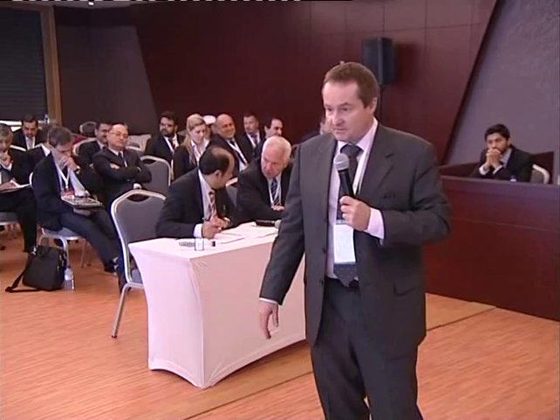Okay, so if you have a certain output of a machine, you can then guarantee that that machine is delivering that output on site? Yes, more or less under actual conditions. Could you maybe give a bit more information on that side? Especially I would like to touch the subject on the VRF system because it's quite a new and very innovative system. It's very easy to commission. Traditionally with air conditioning units you used to do it manually, but with a VRF system you can just connect to a laptop and see all the parameters. It's like checking the parameters of a district cooling plant or a chiller on the screen. So you can get all the parameters like subcooling and superheat and the discharge pressure and temperature. So it's easy in commissioning.